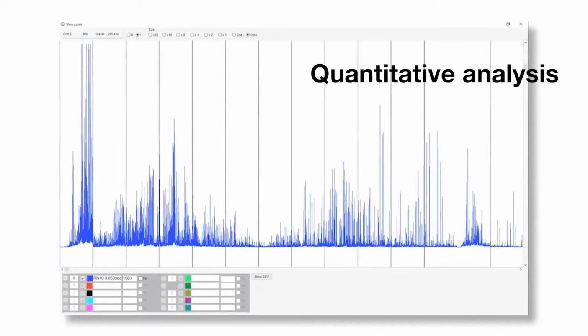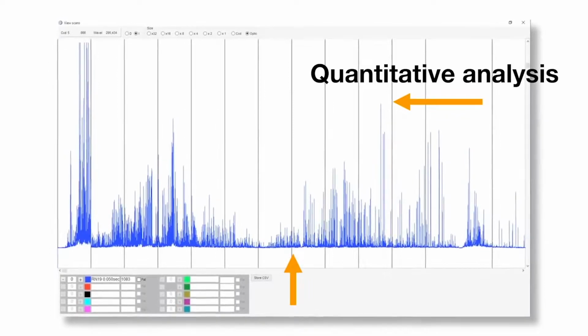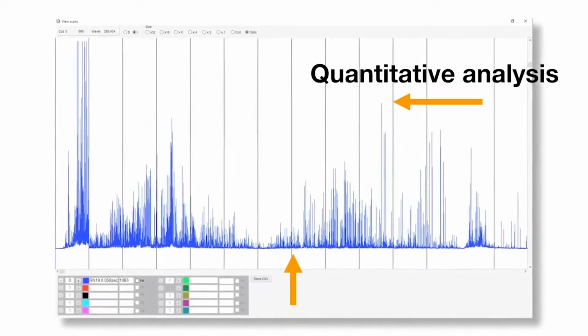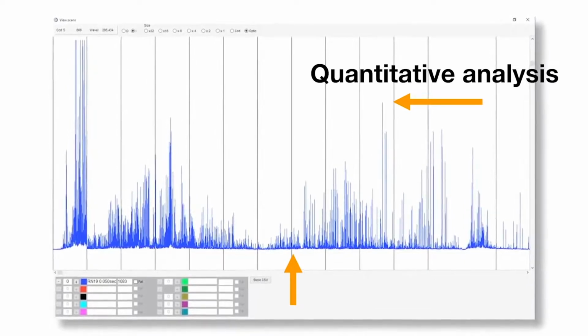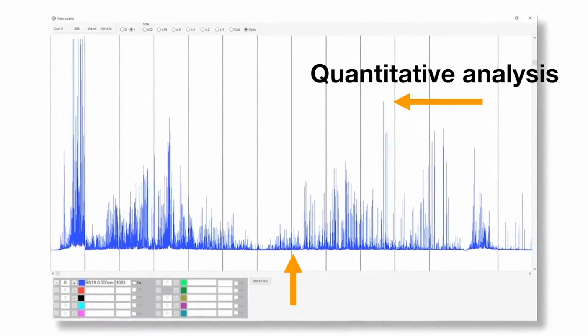However, OES is also a quantitative technique. As we can see, the peak wavelengths identify the element and its peak area or intensity gives an indication of its quantity in the sample. The analyzer then uses this information to calculate the sample's elemental composition based on a calibration with certified reference material. The whole process, from pressing a start button or a trigger to getting the analysis results, can be as quick as 3 seconds, or it can take up to 30 seconds for a full, accurate quantitative analysis. It all depends on the analyzer used, the range of elements measured, and the concentrations of those elements.